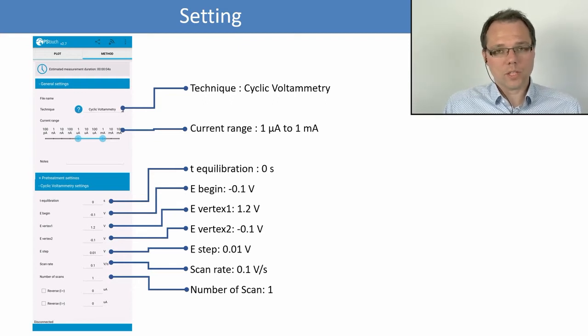Modern potentiostats usually have auto-ranging. That means you can choose multiple current ranges, just like here for the Sensit Smart, and the potentiostat will change the current range if it thinks that's necessary. Then we have an equilibration time, so a waiting time of 0 seconds, which makes the measurement also a bit quicker.